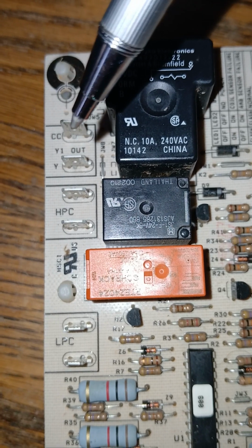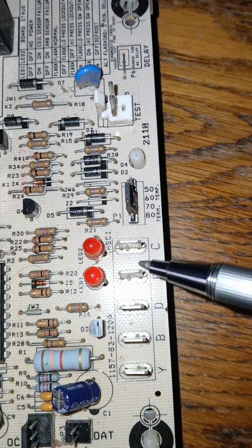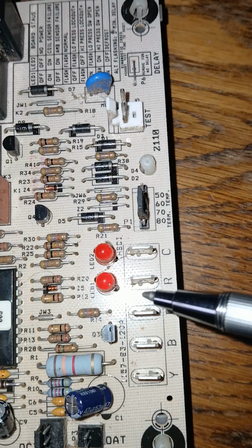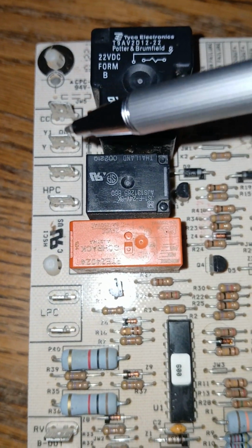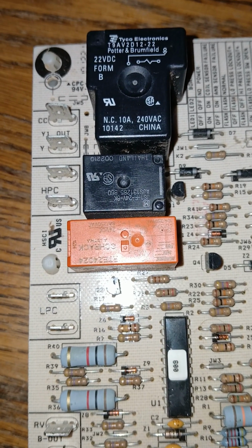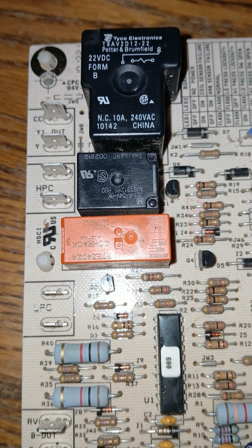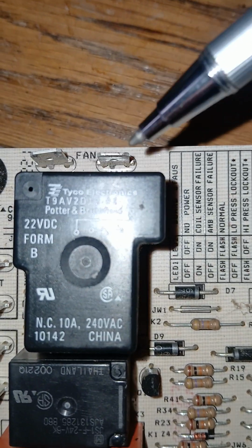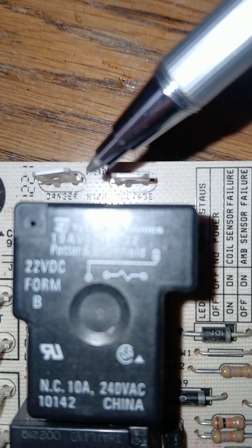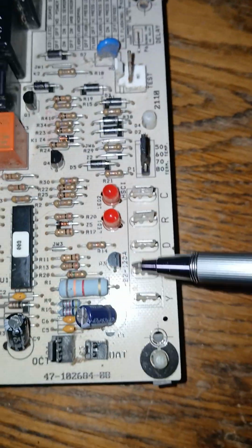I'm not certain on this nomenclature, but as we see here, we have a Y, which would be hot. When the red is jumpered over to Y and energizes this, the Y would be hot and the common would be common, and this would energize the contactor, which would give you high voltage, which in turn could power up the fan or something, because it says here that the fan is danger, high voltage. So this is high voltage, this is low voltage.